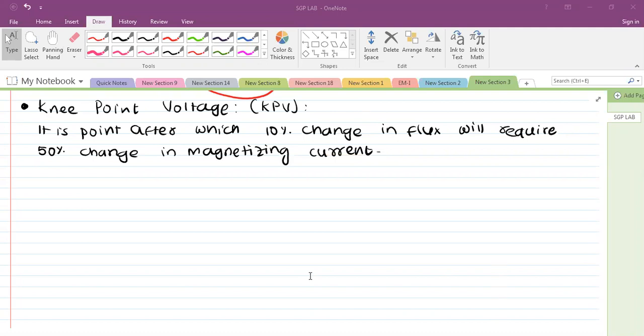I'll tell you the reason. It's a very basic question, you have studied this. What is the magnetizing current requirement of any transformer? It is generally 3 to 5% of the rated load current. Suppose the rated current of a transformer is 100 ampere, it may take 3 to 5 ampere current to magnetize the core from the primary, of its rated capacity. Got it?